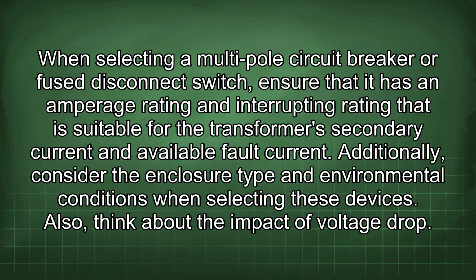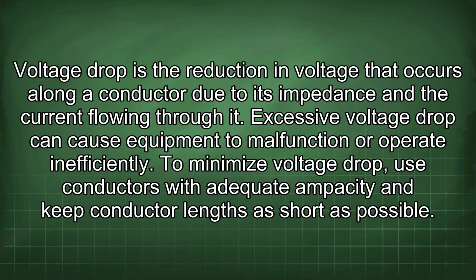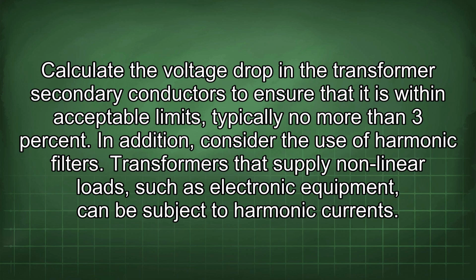Also, think about the impact of voltage drop. Voltage drop is the reduction in voltage that occurs along a conductor due to its impedance and the current flowing through it. Excessive voltage drop can cause equipment to malfunction or operate inefficiently. To minimize voltage drop, use conductors with adequate ampacity and keep conductor lengths as short as possible. Calculate the voltage drop in the transformer secondary conductors to ensure that it is within acceptable limits, typically no more than 3%. In addition, consider the use of harmonic filters.